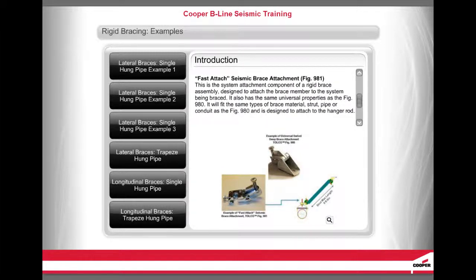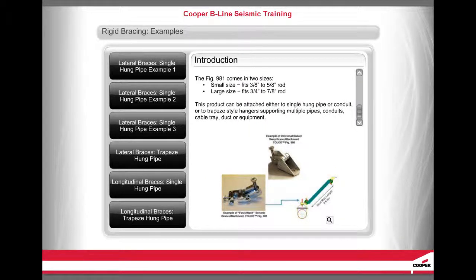The Fast Attach Seismic Brace Attachment, Figure 981, is the system attachment component of a rigid brace assembly, designed to attach the brace member to the system being braced. It has the same universal properties as the Figure 980, fitting strut, pipe, or conduit, and is designed to attach to the hanger rod. The Figure 981 comes in two sizes: small fits 3/8 inch to 5/8 inch rod, and large fits 3/4 inch to 7/8 inch rod. It can be attached to single-hung pipe or conduit, or to trapeze-style hangers supporting multiple pipes, conduits, cable tray, duct, or equipment.